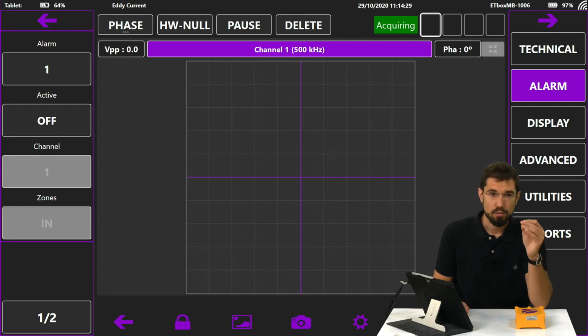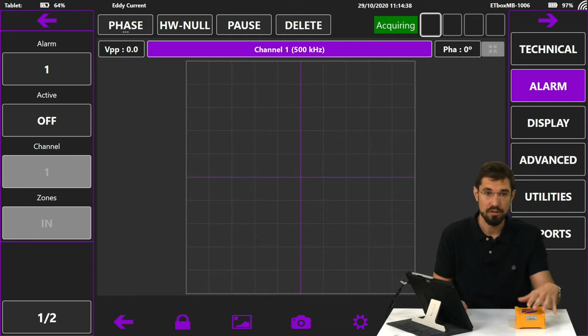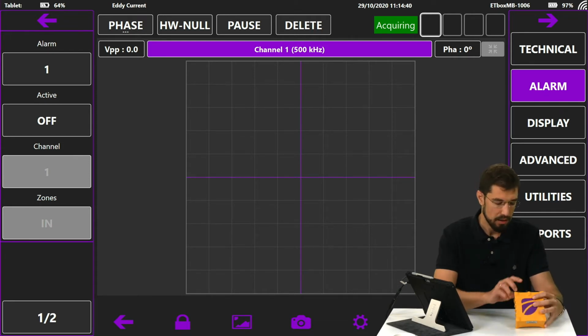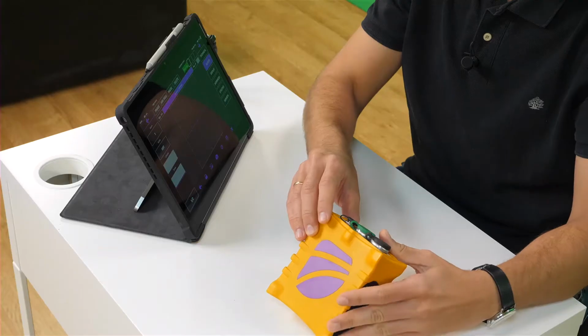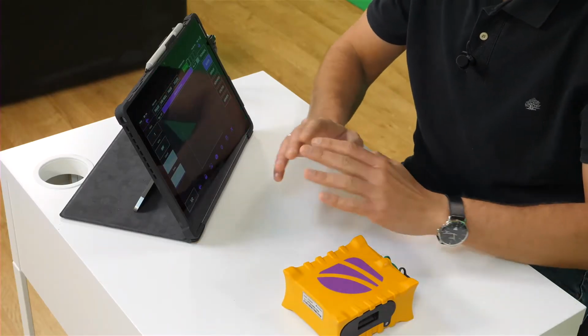This application is very flexible and completely customizable depending on the needs of our inspection and the nature of our signals. We can also configure it so that the instrument creates an alarm and generates an exit through its digital output. This gives us endless possibilities.